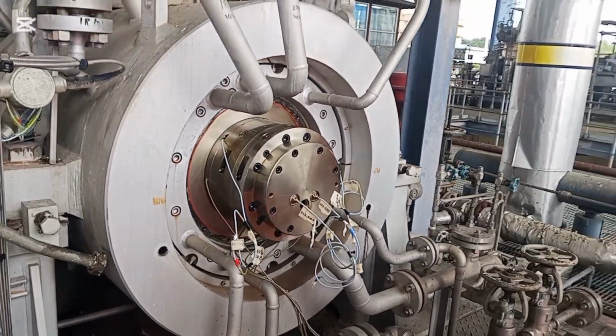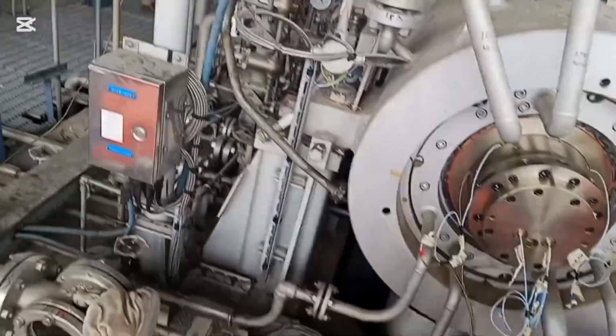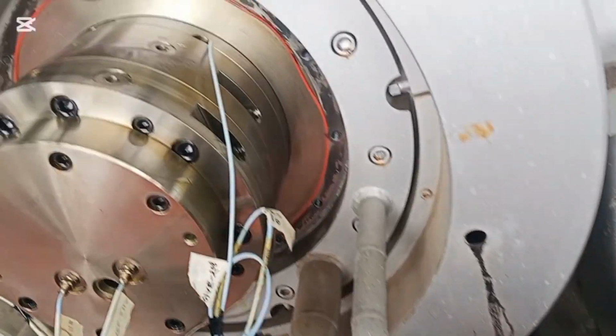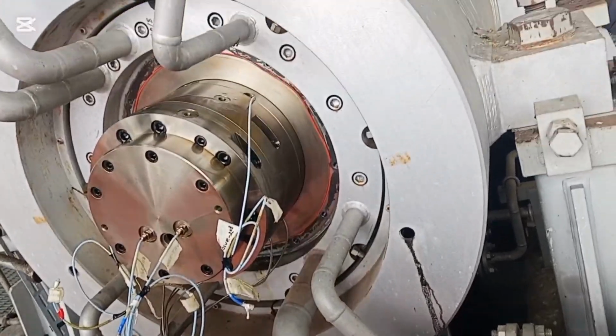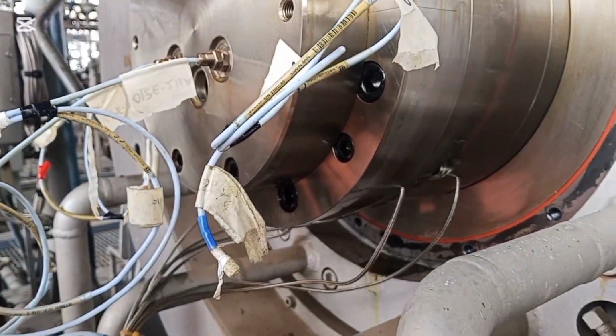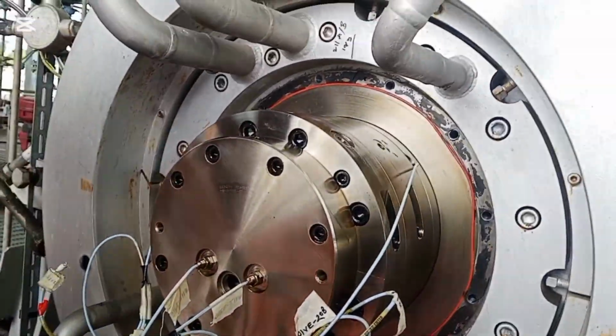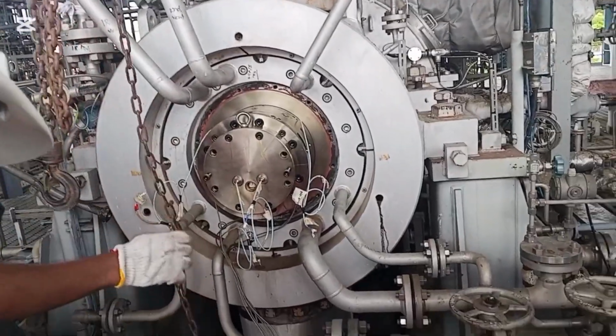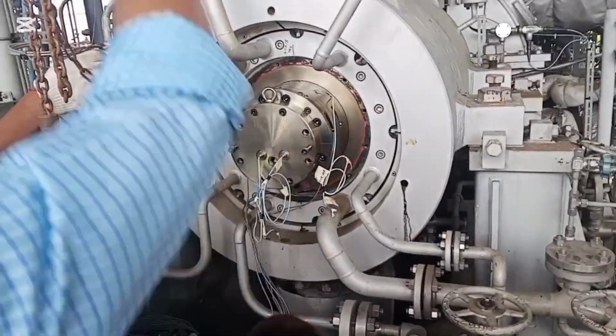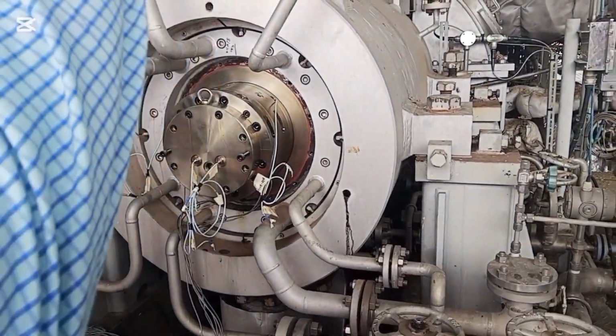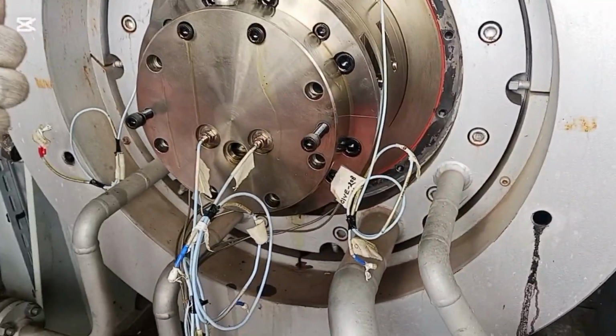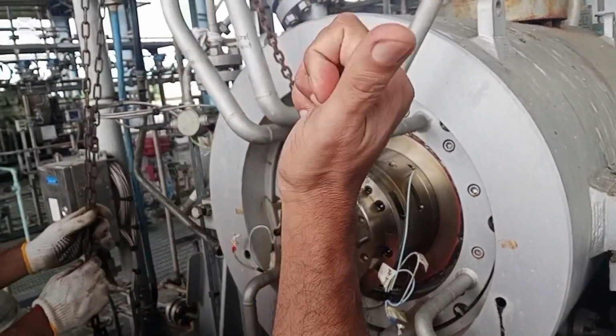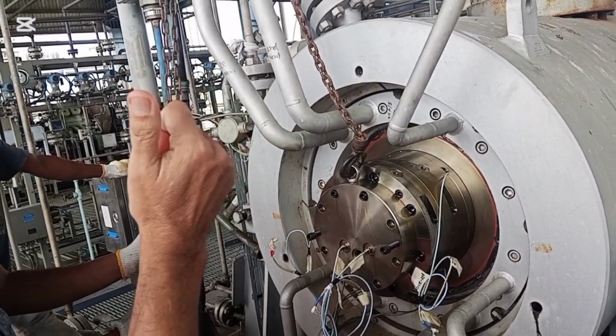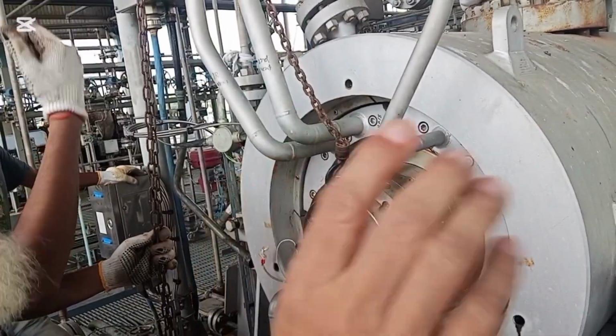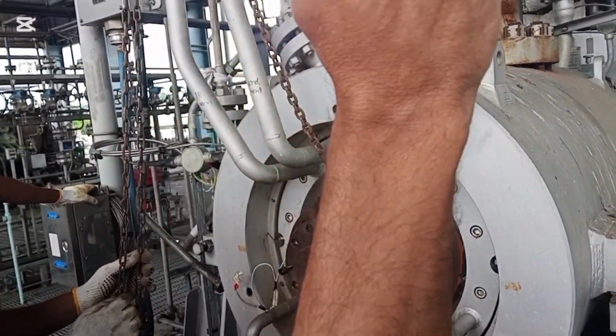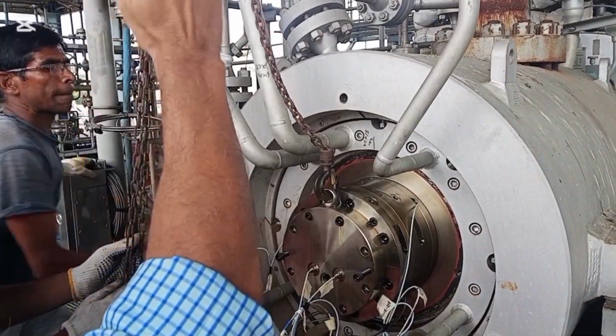First, remove the vent line and end cover blind from the non-drive end, and then remove the oil drain line of the non-drive end. Then remove the end cover thrust side, and disconnect all related instruments, that is the RTD and vibration probe. Then remove the coupling cover and associated parts between the turbine and high pressure barrel. After this, remove the coupling spacer, then remove the OS damper housing, the axial displacement probe carrier and part number 41, and then check and record the thrust bearing clearance at the time of maintenance. Different readings, that is clearances, we measured for safety and for assembling again.